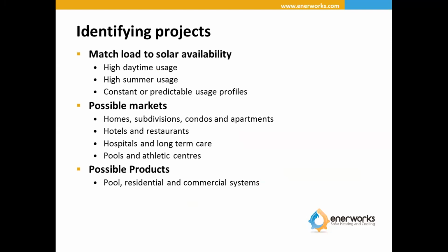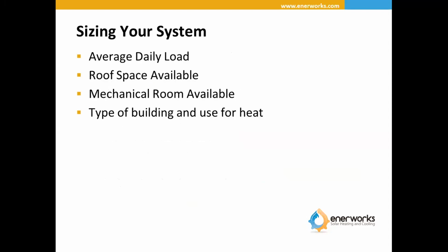So, identifying some of the projects: if you have a higher daytime use, higher summer use, is it a constant, predictable load? We're going to talk a little bit more about some of the information that we require that's different than what you might use to size, say, faucets or a conventional water heater. Solar works on an average daily load. I think ASHRAE might actually have some standards for this, whereas your hot water system is often designed for your peak load. Solar is designed for the average. So if you take that average and say it's 1,000 gallons a day, it might be higher one day, lower the next, but the average is, say, 1,000.